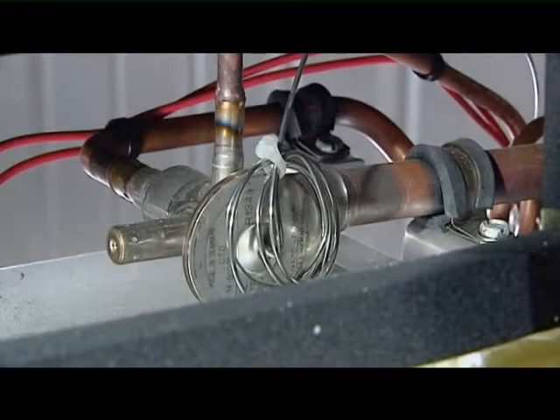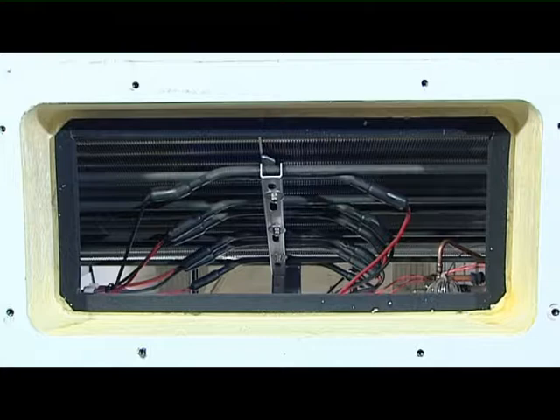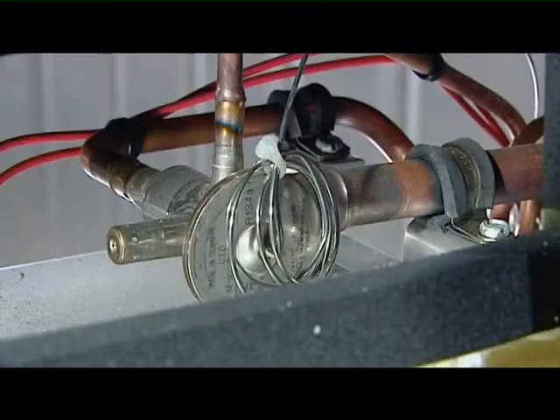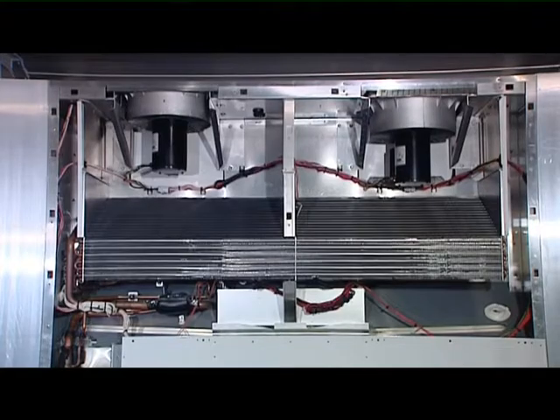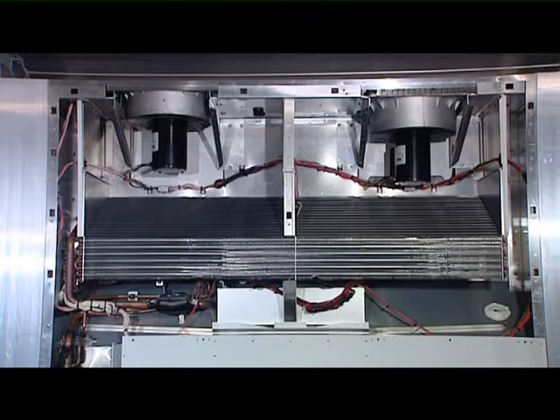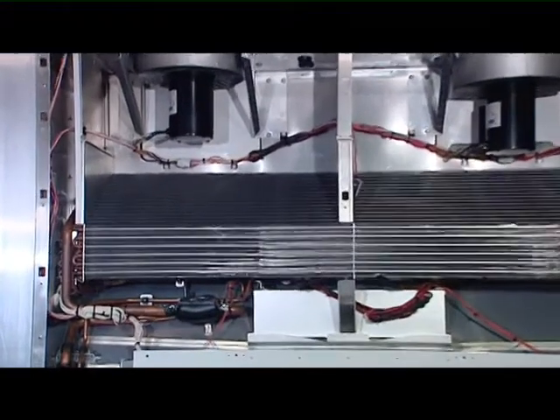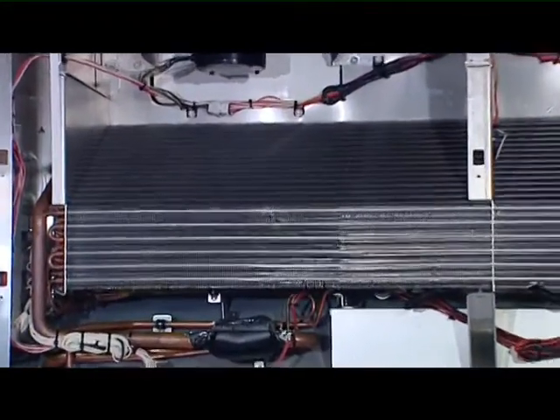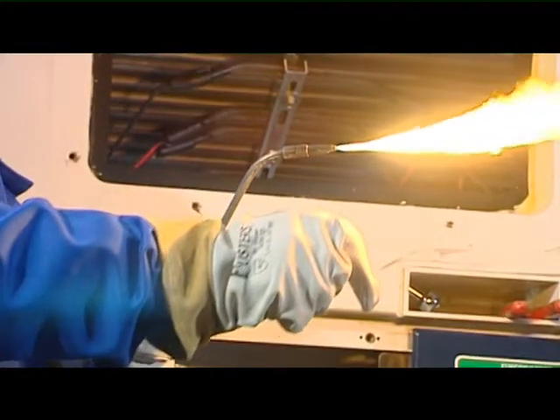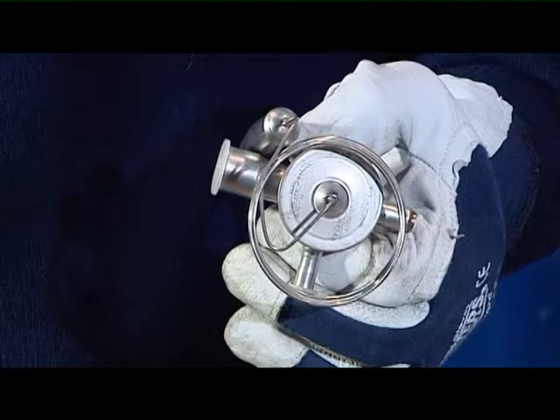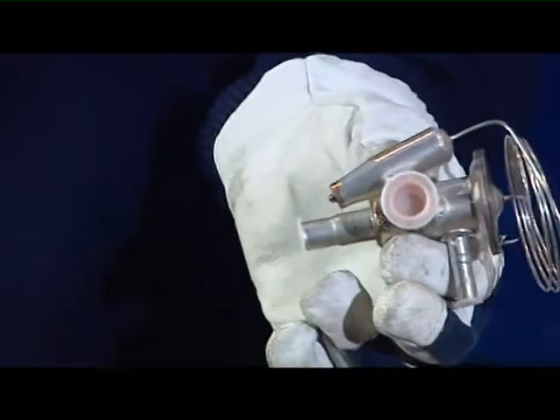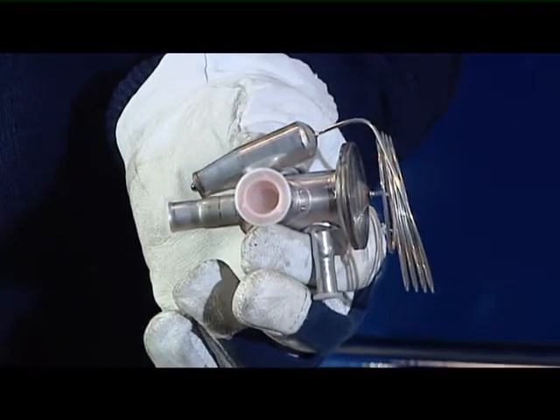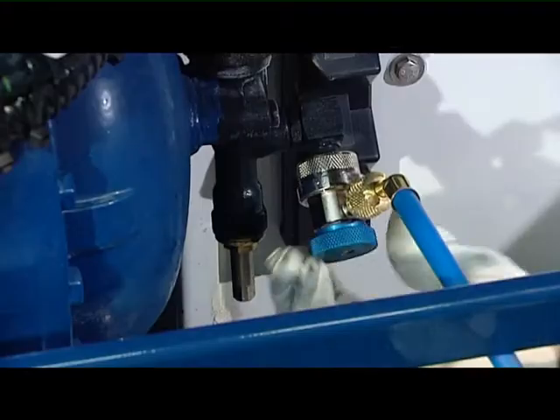Thermostatic expansion valve. This valve prevents liquid refrigerant entering the compressor and controls the amount of refrigerant entering the evaporator coil. The thermostatic expansion valve is not adjustable and when defective has to be replaced. All connections on the hermetic valve are bimetallic, copper on the inside and stainless steel on the outside. All joints on this valve are brazed.